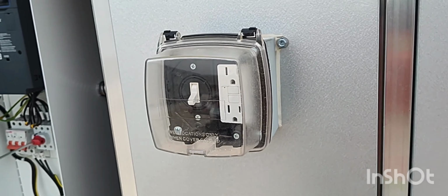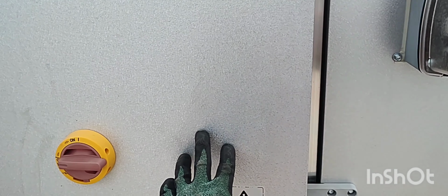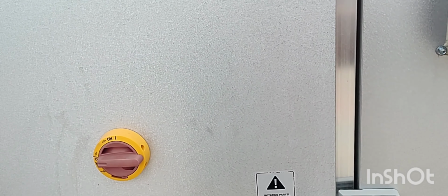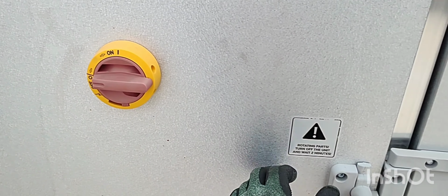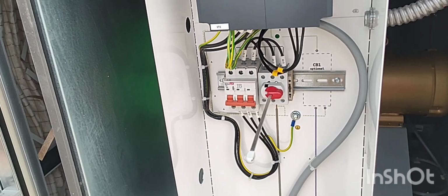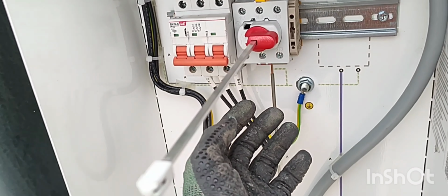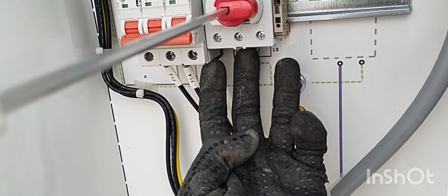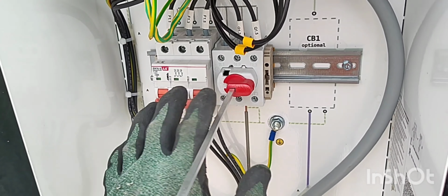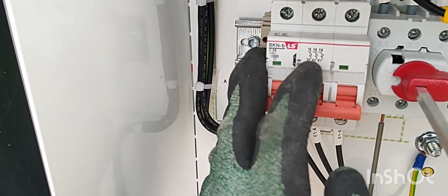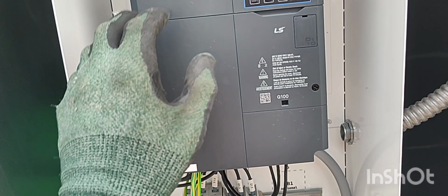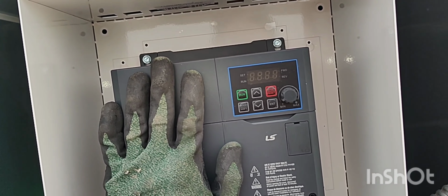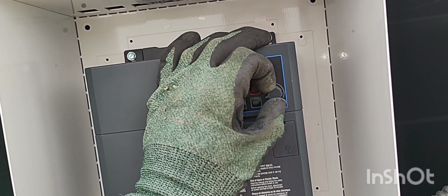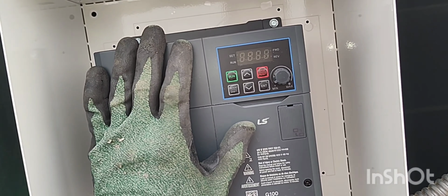We need to size our disconnects to that motor. Or sorry, our conductors for that motor. So right here's our disconnect that attaches to this bar. Our lines are going to come in right here, line 1, line 2, line 3. Off of this, it's going to go through our overloads. From that symbol right there, you can tell they're heaters. And then to our VFD, our variable frequency drive. This controls the speed of the motor.